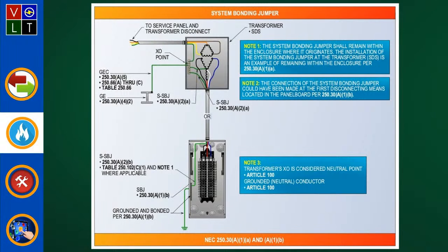Yeah, it was basically a replica of 250.66, because that was the 12.5% on circular mils, right? That's right. And that's actually what 250.102(C)(1) was, but they made it Table 2, or at that time 250-94. Now they went back, and that's what he was trying to say when he was doing that course. Table 250.102(C)(1) was essentially based on that multiplier based on the overcurrent protection device, to get your circular mils to size those conductors that were in that table.